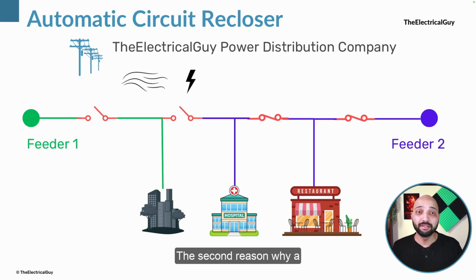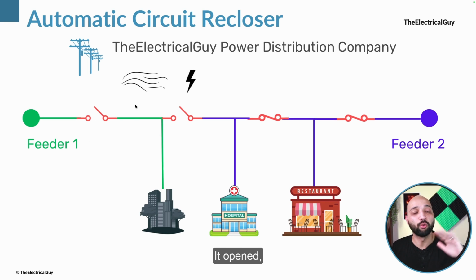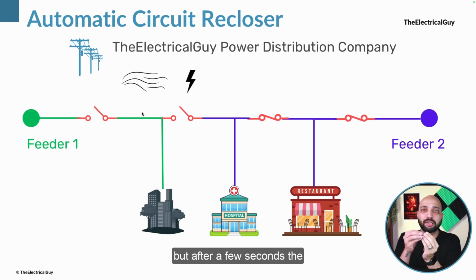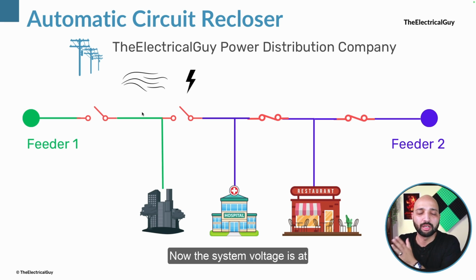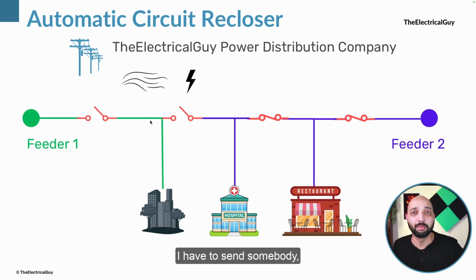The second reason why a temporary fault can occur is a lightning stroke. Let's say there is a lightning stroke. My circuit breaker senses it's an abnormal situation. It opens, but after a few seconds, the lightning stroke has gone. Now the system voltage is normal, but still I have to send somebody to check and manually close the breaker to restore the power supply. Again I'm losing money and time here.